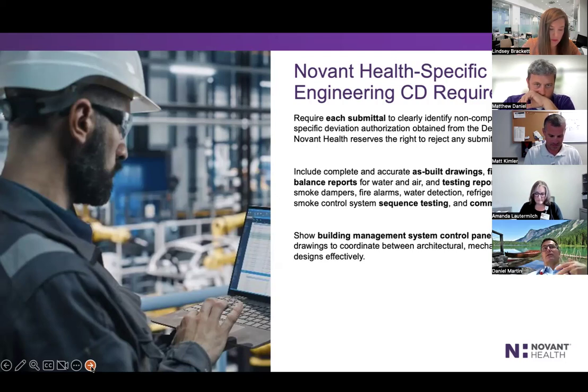We also want to make sure we're getting testing reports for those fire dampers, because 1 year after construction you've got to test all those fire dampers and make sure they're operational. The fire alarm you'll be testing quarterly, along with water detection and refrigerant detection. One thing that really got us on one of our projects here was we changed out 2 chillers, and what was overlooked was that the refrigeration alarm didn't cover the new refrigerant. We found that out during one of our inspections, which helped with that so-called commissioning that was missed, even though one of our other chillers already had that same refrigerant, the sensor we had did not cover the new one.